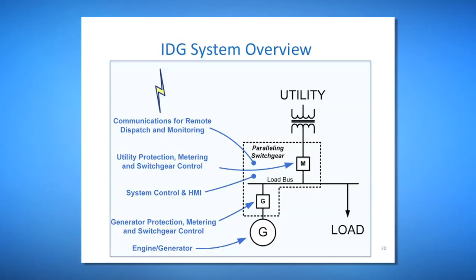When we peel the onion back a little, what do we have? Communications for the dispatch and the monitoring, and utility protection, because utilities don't like you to parallel with them unless you do certain things. It's called IEEE 1547, a standard. If you do all that, the utilities are cool with it. They all have their own rules too, but it's based on 1547. You have system control and HMI, then the generator protection and metering, and finally the engine generator.